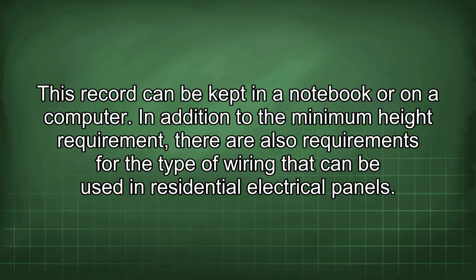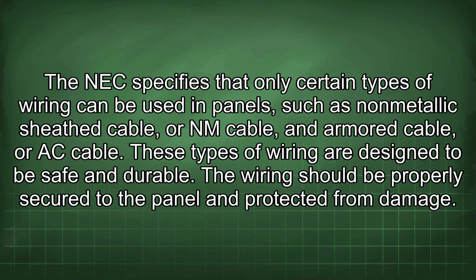In addition to the minimum height requirement, there are also requirements for the type of wiring that can be used in residential electrical panels. The NEC specifies that only certain types of wiring can be used in panels, such as non-metallic sheath cable, or NM cable, and armored cable, or AC cable. These types of wiring are designed to be safe and durable. The wiring should be properly secured to a panel and protected from damage.